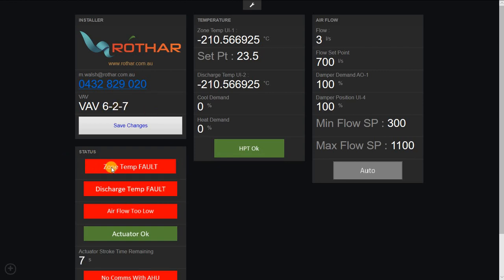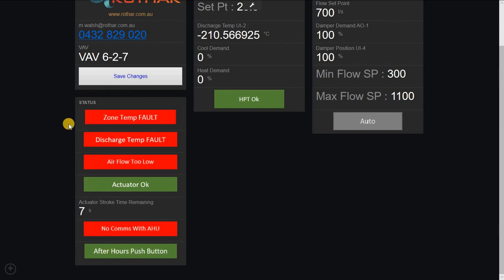We have this status, which can tell you what's going on. So we have a block for our occupancy light. We use the Distech override sensor, which has a push button and a LED. We use the push button to enable the after hours, which you can see here. We also use the LED light to offer feedback to the users and to the techs walking around the floor so they can quickly see which VAVs are having some difficulty.